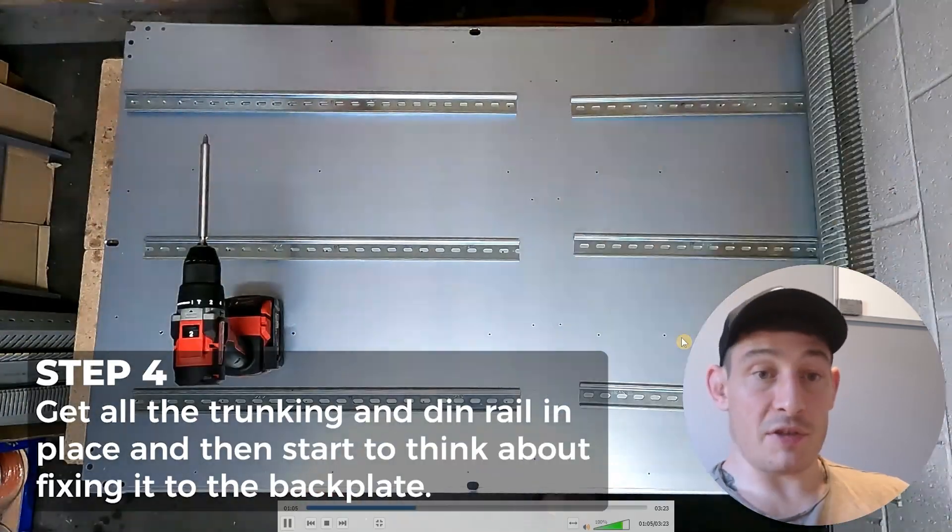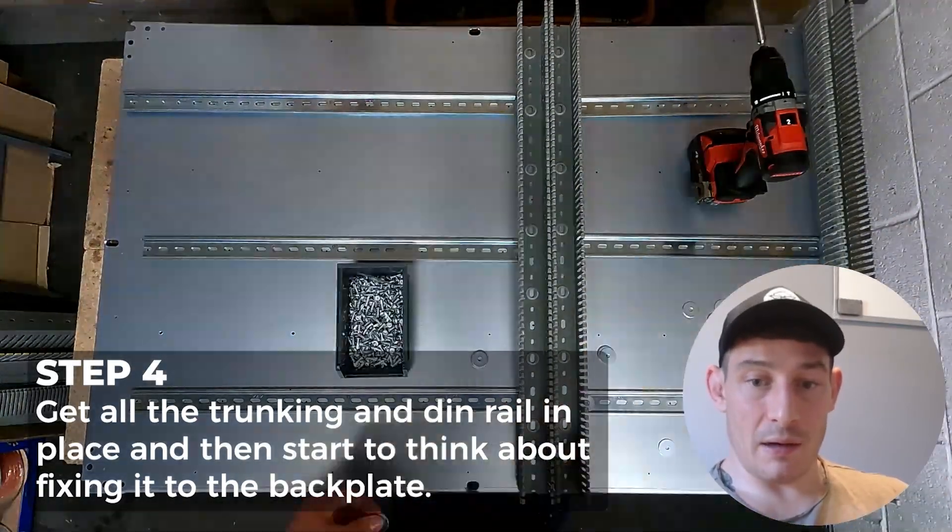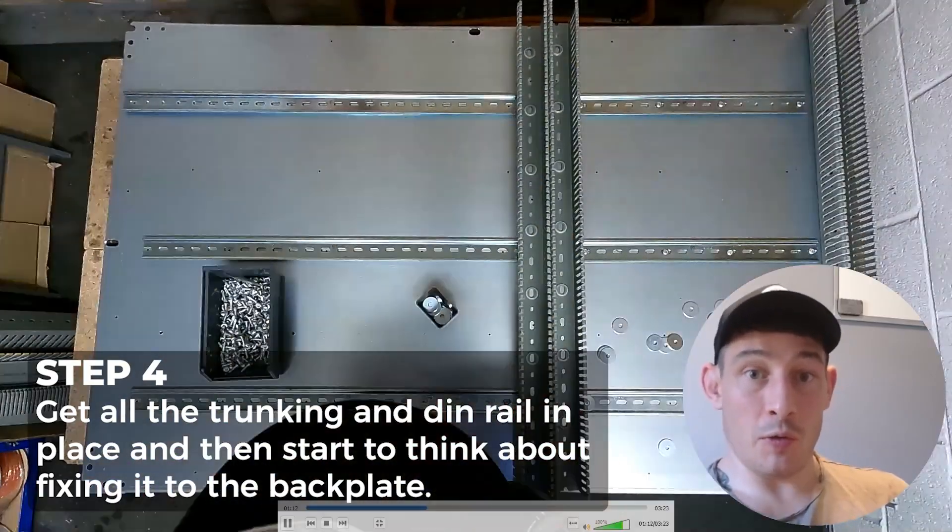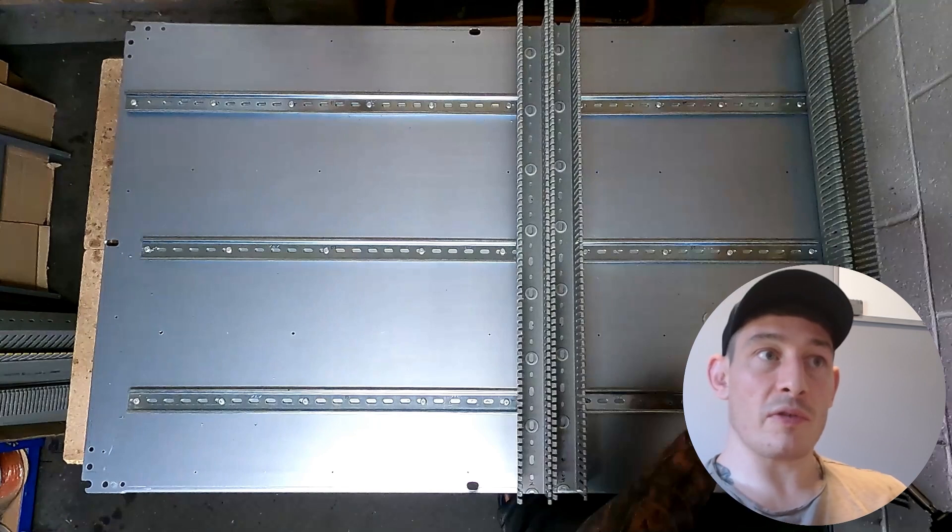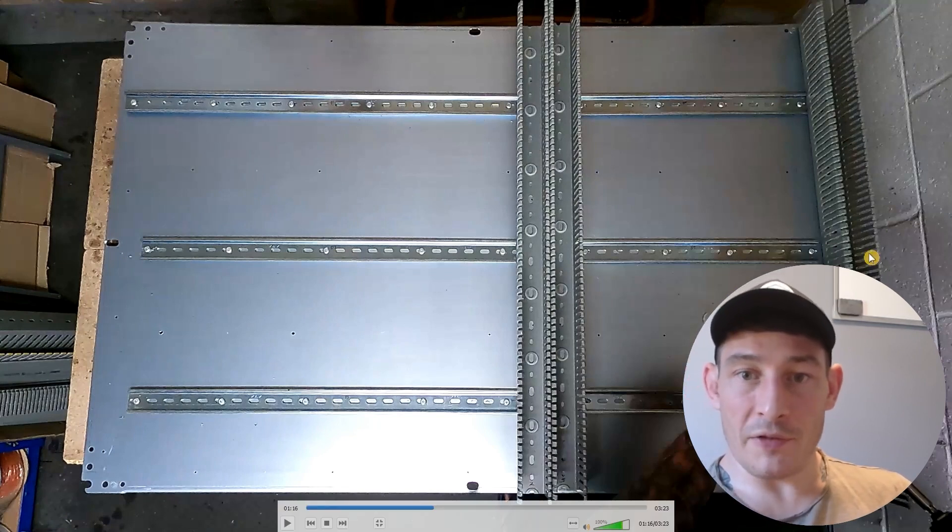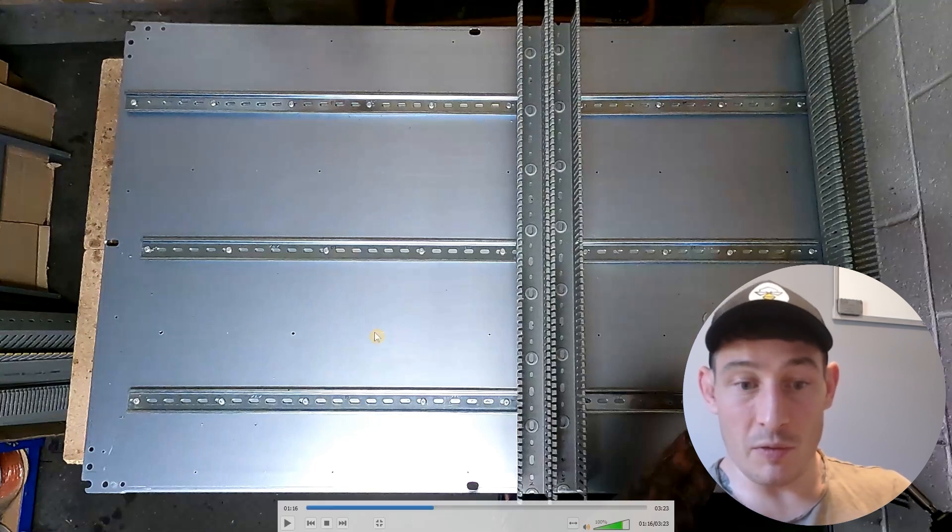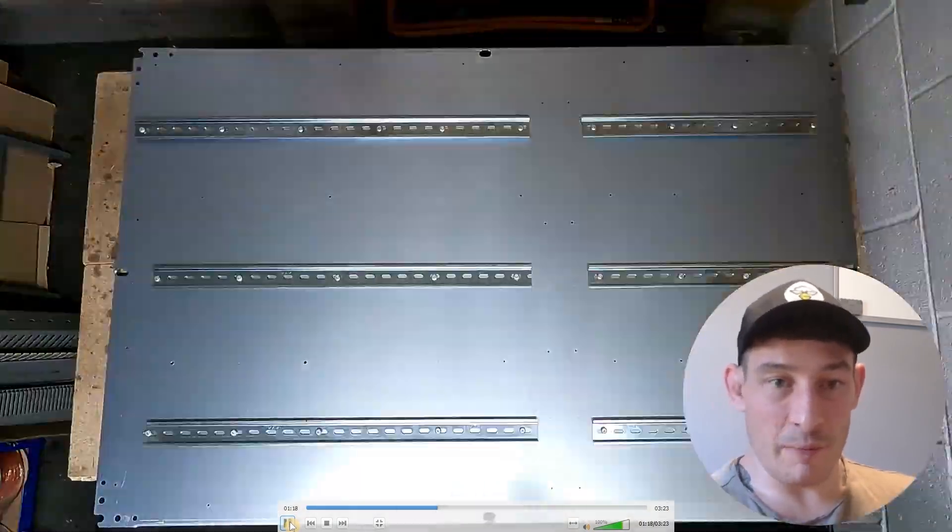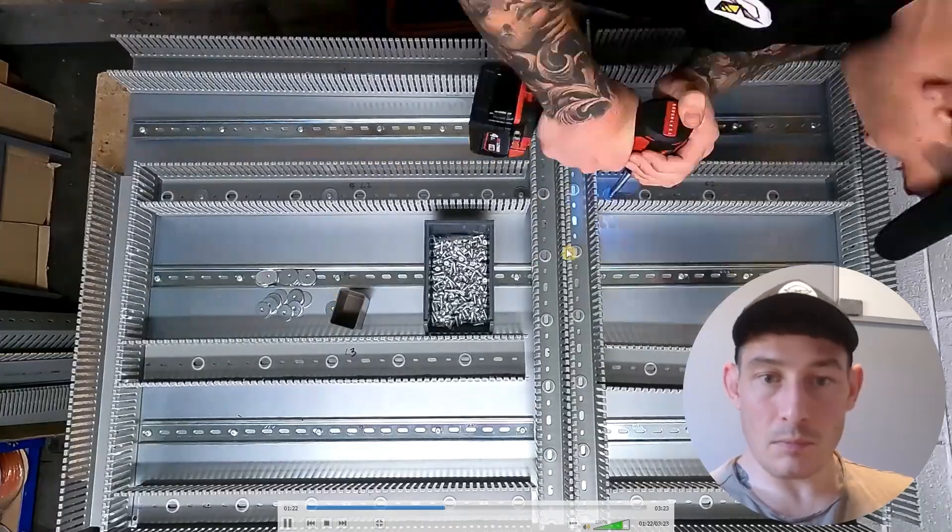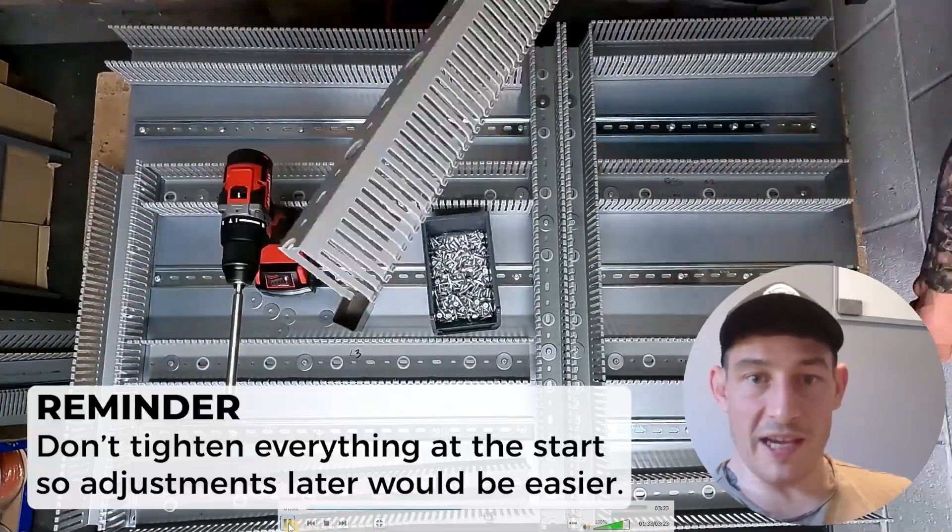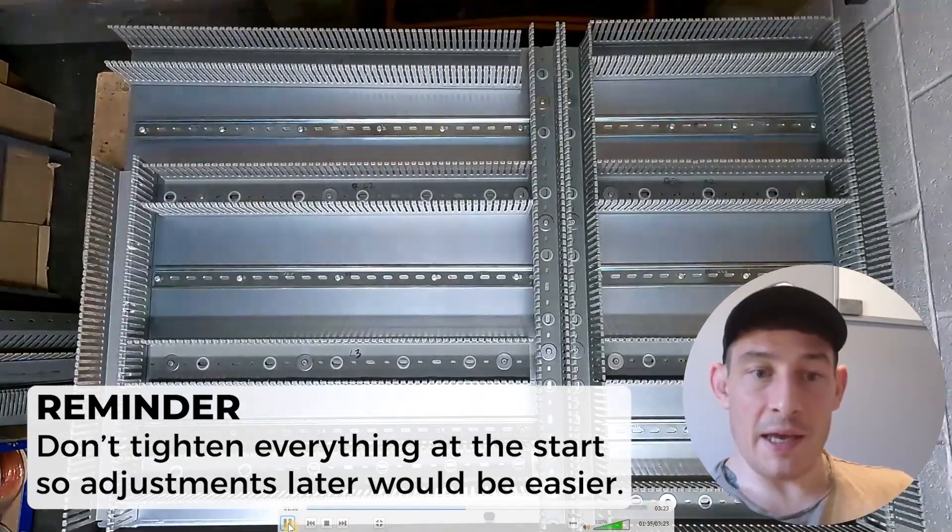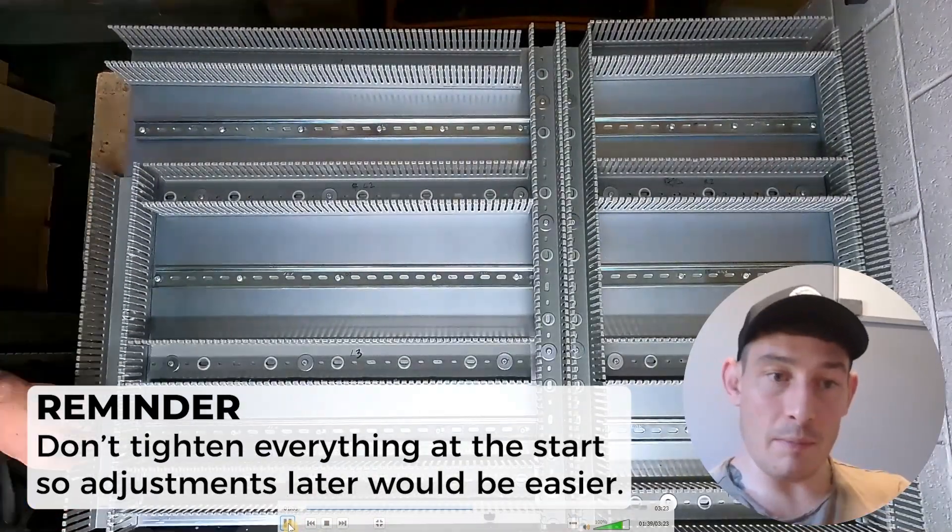So now just a matter of getting all the trunking and DIN rail in place and then starting to think about fixing it to the back plate. So as you can see you could use penny washers for the DIN rail as well. I think I didn't have enough to be consistent, I would have ran out about halfway through this side here, so I'm just fixing using tech screws which is good enough for me. And then the actual trunking I'm using penny washers, and I don't know if you can see it here but I'm not tightening anything fully yet. I'm leaving it all a bit loose so they can move about.